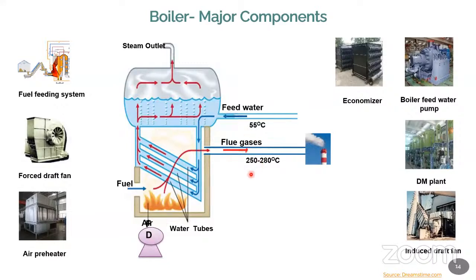So that is why flue gas monitoring is very, very important. Most of the industries having boilers will regularly check the flue gas. What is the temperature of the flue gas? What are the contents in the flue gas? We have separate flue gas analyzers available. I showed you in yesterday's class. In the flue gas, what is CO, what is CO2, what is O2, what is the excess air? Everything will be properly monitored and measured with the help of a flue gas analyzer.